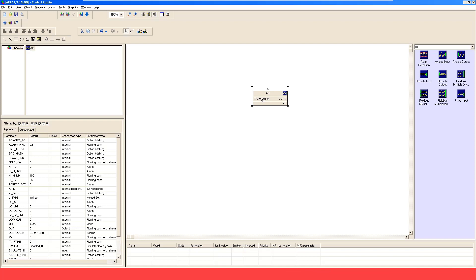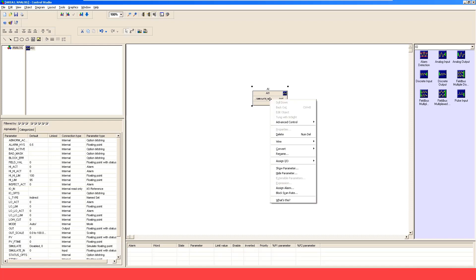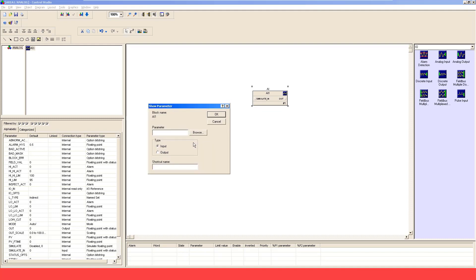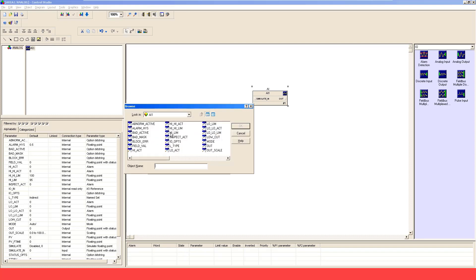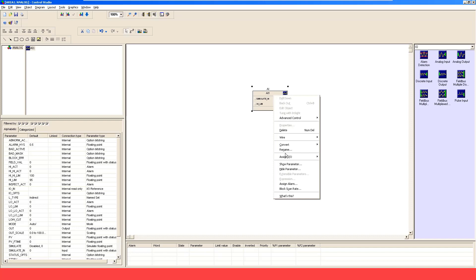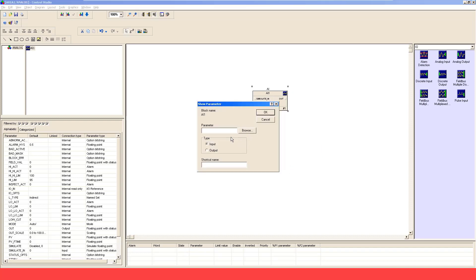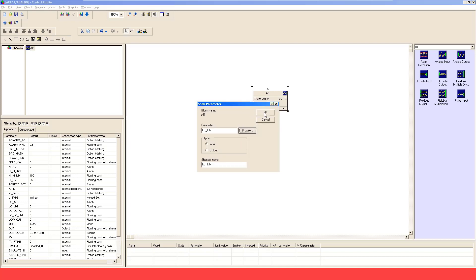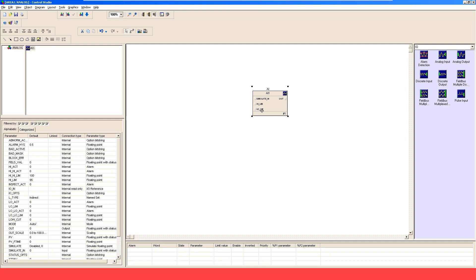By default this particular function block doesn't have everything. If you want to add a few other things which are important for our analog signal processing, right-click and select Show Parameter, then select Inputs. Whatever you want to get into the input side of this block, select Input and Browse. First I'm going to add High Limit — select OK. Then right-click, Show Parameter, Browse, at the Input side, and add Low Limit as well. So now we have added High Limit and Low Limit.